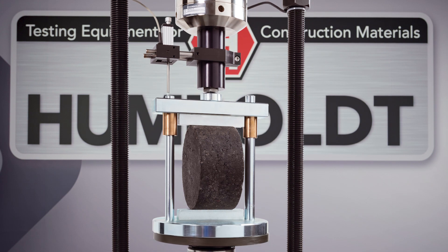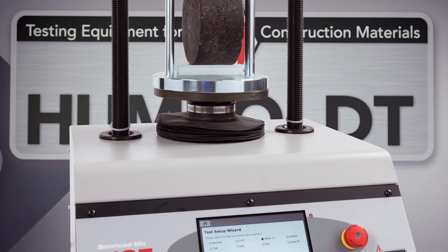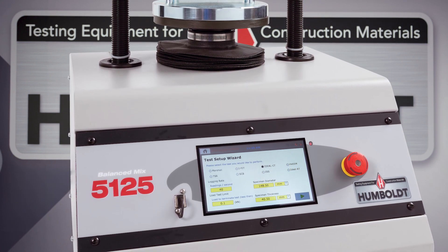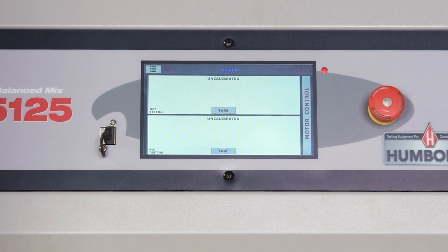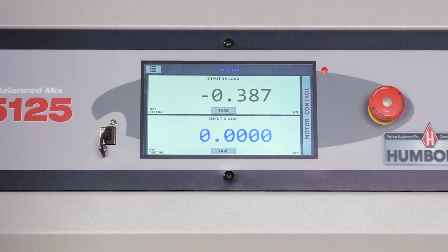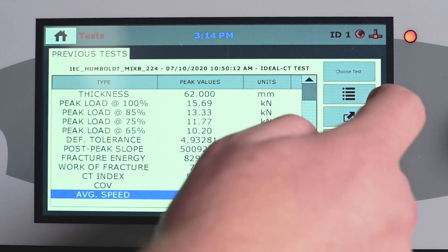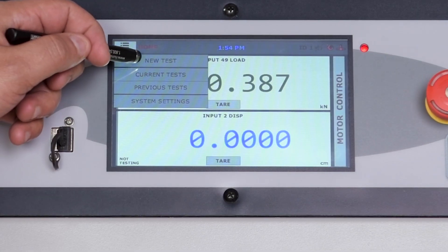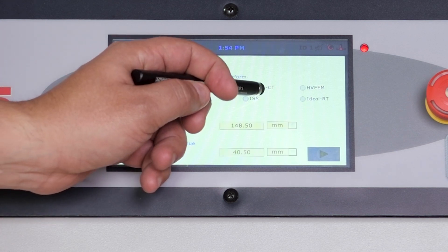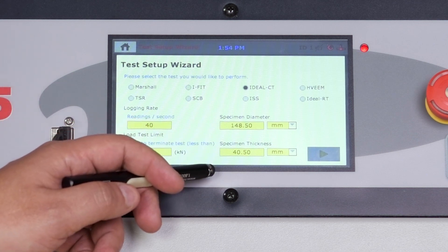Humboldt's HM5125A.3F load frame has been designed to provide precise test rate control for the automated testing of asphalt balanced mix design samples. The HM5125A is built around Humboldt's integral data logger with touchscreen control, which allows the load frame to be used as a standalone device capable of full test control and data logging. Operators can see all the data in several formats at the machine during the testing procedure. The easy-to-operate HM5125A load frame allows you to quickly choose your test and its parameters in the test setup wizard for automated operation of the testing process and results.